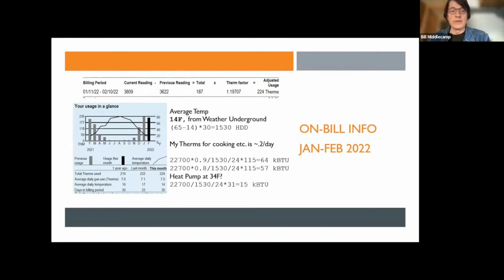So it's 22,700 BTUs times my furnace is about 90% efficient, divided by the heating degree days for the month, and I got that by taking that average temperature times the number of days in the billing period, 1,530 heating degree days, divide by 24 to convert it to hours, times this heating rise that I need, and I came up with my need was 64,000 BTUs. Now, if I go back and correct it for the number, which should have been 224, this 64,000 is going to be lower than that.